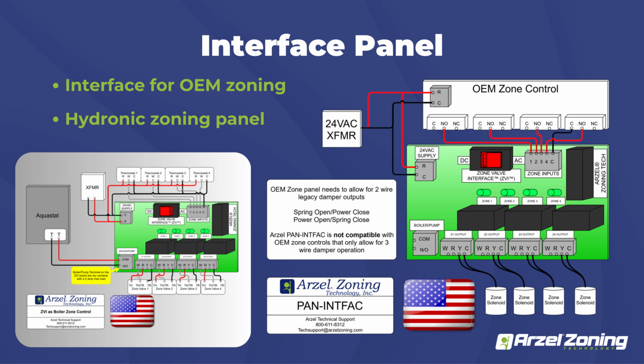This is just kind of another diagram. As you guys can see in this one, it uses the same exact board. So in this instance here, it's using it to control the boiler. In this instance, it's actually using it to interface with a communicating piece of equipment. If you guys don't know, Arzel's panels are not compatible with communicating equipment directly. So if you guys are going to do it, we can piggyback off of some of the manufacturers' communicating equipment, but it has to be a 2-wire system. We're not compatible with 3-wire zoning panels, so we would not be able to adapt to that. But if they give you the capability of doing a 2-wire system, you can incorporate a communicating piece of equipment. You would use their zoning panel to control the equipment.